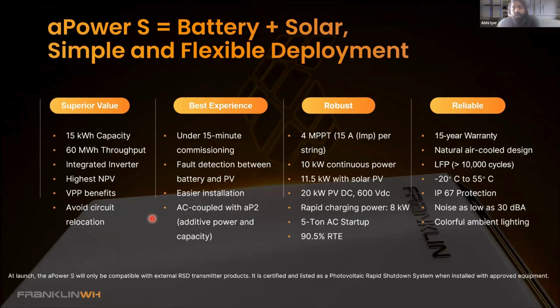The round trip efficiency on the aPower S is 90.5%, right? So it certainly is higher compared to other battery solutions here. One thing I do want to stress here is the charging power. Like I said, it's a 15 kWh capacity battery, but has 8 kW of charging power, which puts this battery as one of the fastest charging batteries in the industry. You can top off the entire aPower S unit in under 2 hours as long as you have 8 kW of power source generation available.